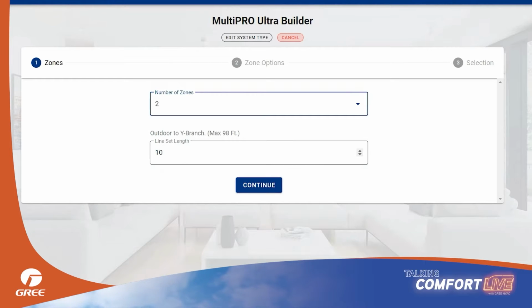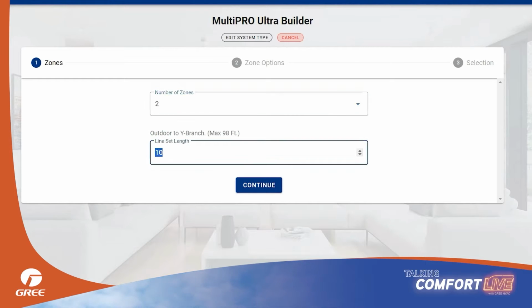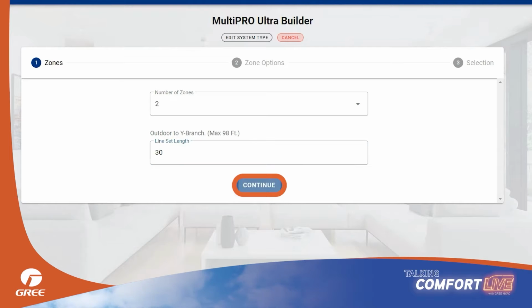Next is the line set length. This can be an estimate, but at some point you need to go in and measure the line sets and enter that information accurately so you can get the proper amount of additional refrigerant charge. In this case, from the outdoor unit to the Y branch might be 30 feet, so we enter 30 feet and click Continue.